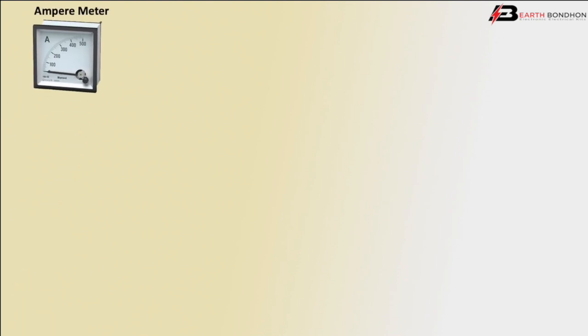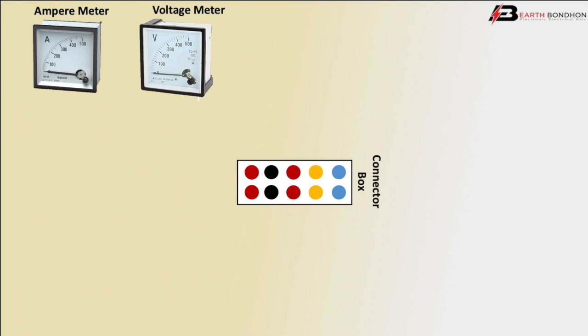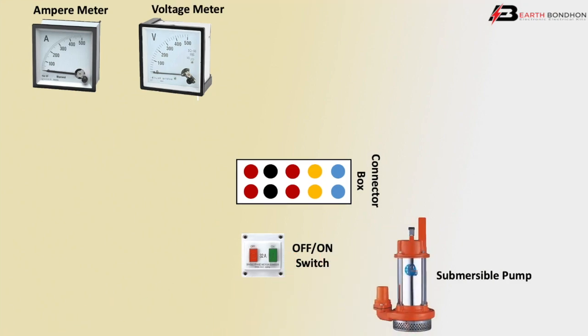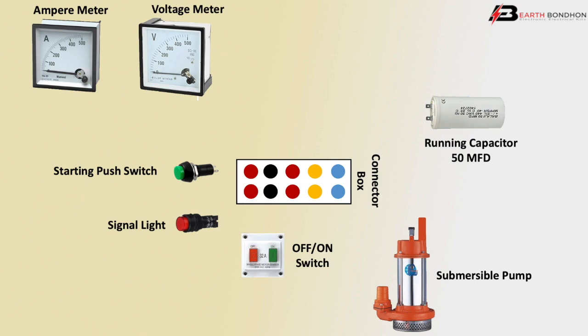First, using the ammeter to show the submersible load capacity, and a voltmeter to show the submersible input voltage. The connector box shows input/output motor connection and mainline connection. The connector box uses an on/off switch, submersible pump starting push switch, and signal light. Components include an indicator light, running capacitor of 50 microfarad, starting capacitor of 150 or 120 microfarad.